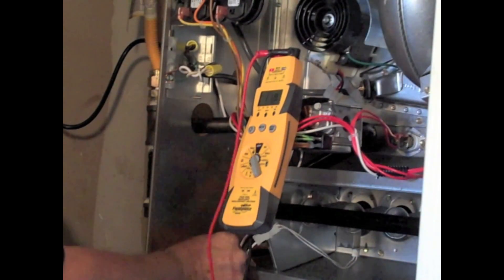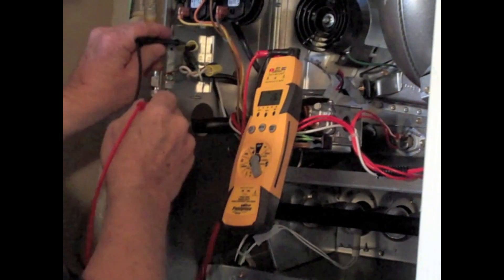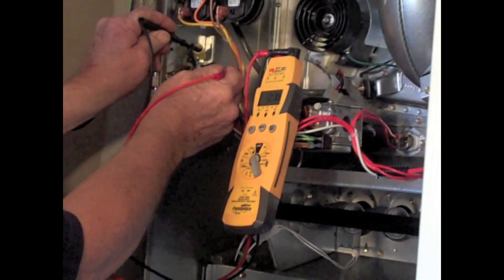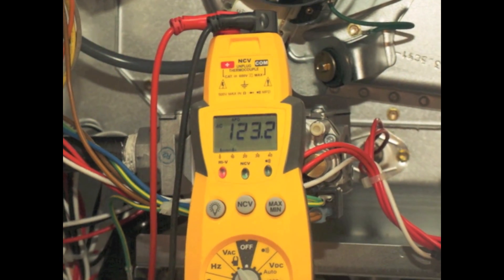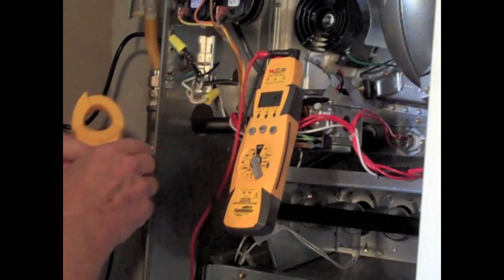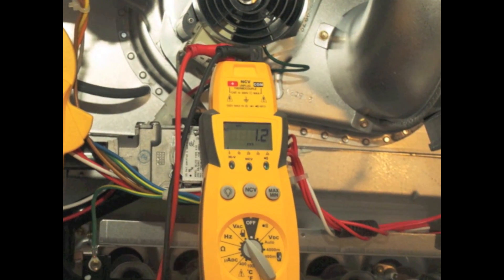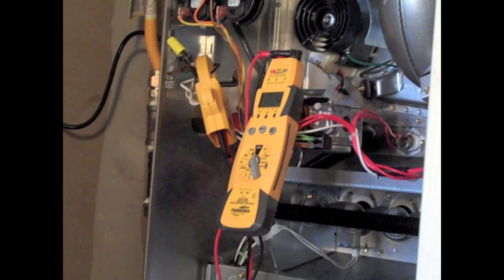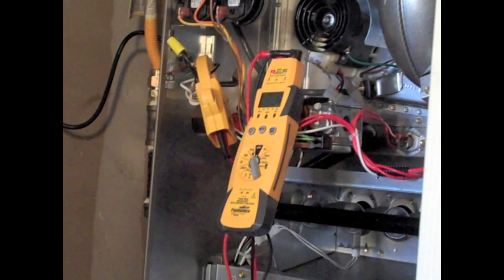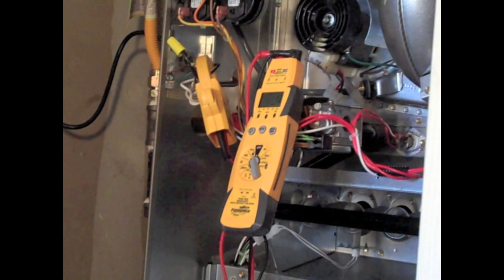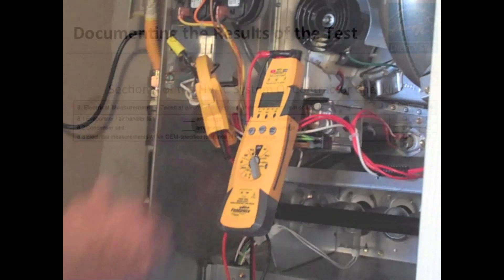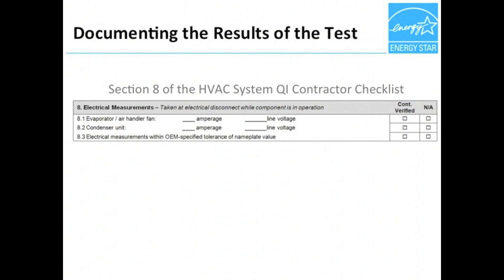Here we see Rob using the digital multimeter to take the measurements. First, he measures the voltage of the disconnect or furnace junction box, and we can see here that the measured value is 123.2 volts. Now Rob is determining the current at the same location, and we can see that he measures a value of 1.2 amps. HVAC contractors should always take special care to safely measure electrical characteristics. When comparing these measured values to those in the manufacturer's documentation, Rob finds that they are well within the tolerance.